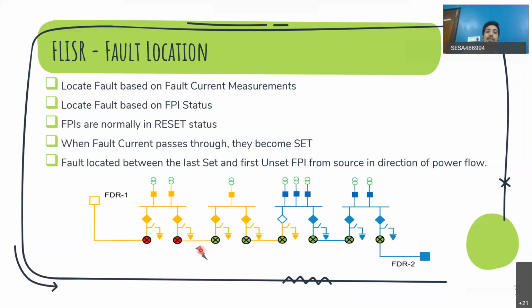So with one single RMU functionality, you are able to identify the fault within a few seconds. Imagine the previous days, from what I understood from one of the utilities: whenever there is a fault, there is a huge fault finding equipment placed in a truck, and they had to travel across streets and pass some frequency and get the resonance. Wherever there is a fault, the frequency of resonance will change. That way they would go across the feeder network to identify it. Imagine if the fault is in the last RMU and that feeder is 10 kilometers long. Sometimes it may take a day or two, but now with the help of this feature, it is just a few seconds. So that is the first part.